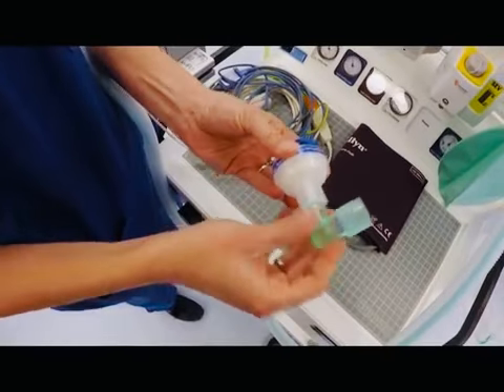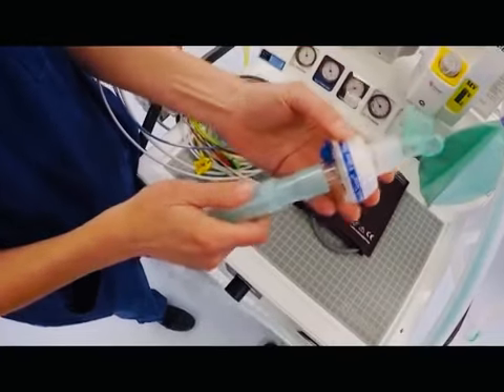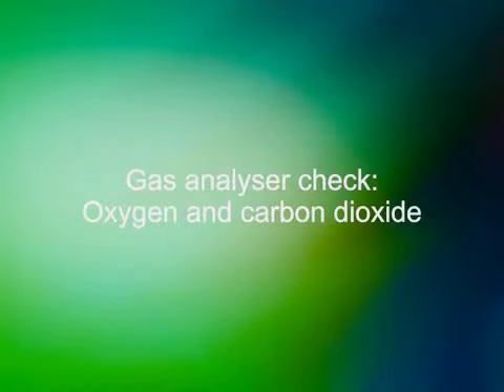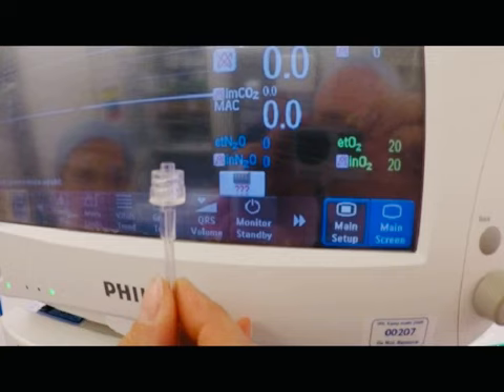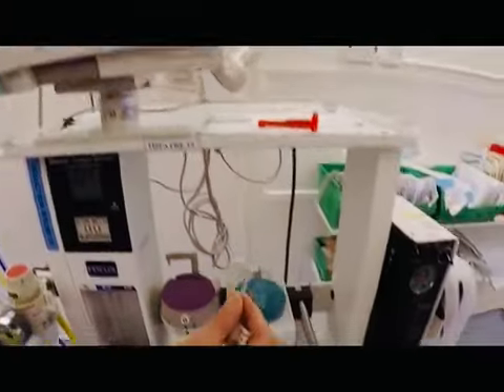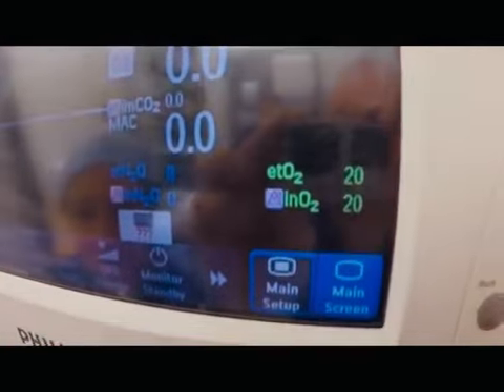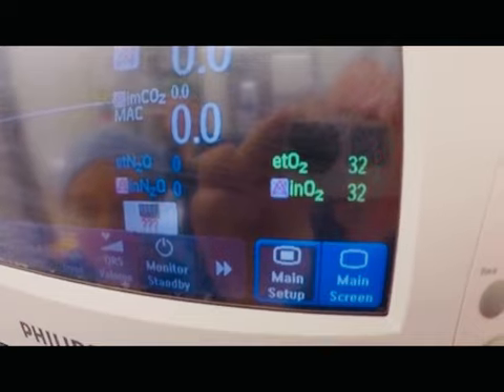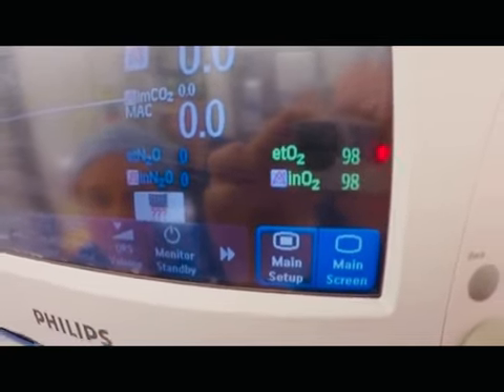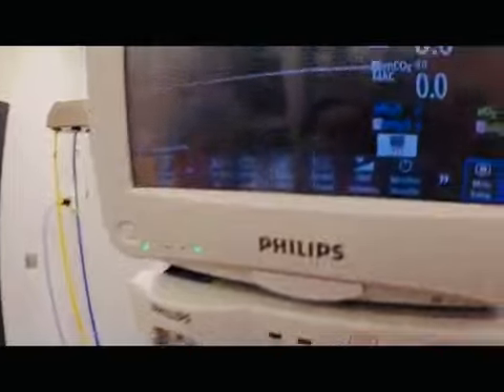Inspect the angle piece and filter for any defects and attach to the Bain circuit. Check the oxygen analyzer at 21% for room air and 100% oxygen by putting the end of the analyzer into the common gas outlet with oxygen switched on. Blow into the end tidal analyzer tubing to confirm measurement of carbon dioxide.